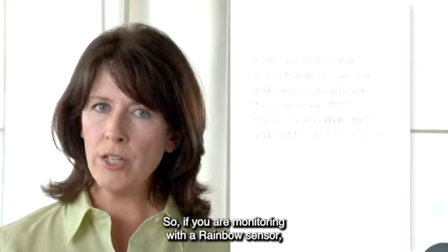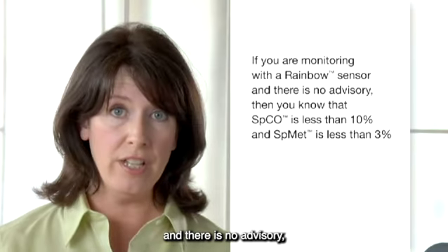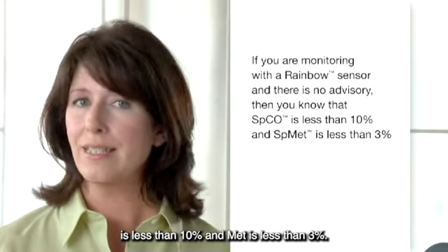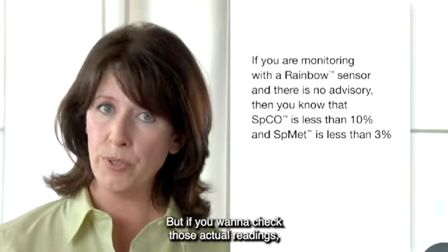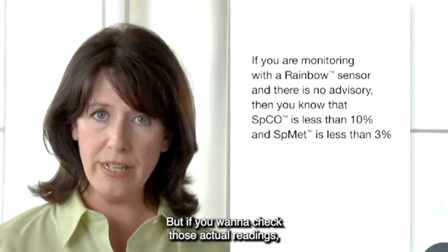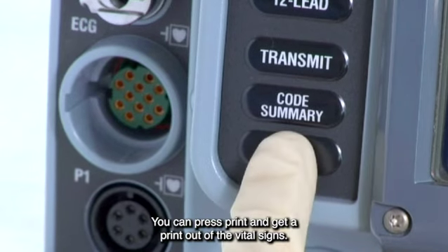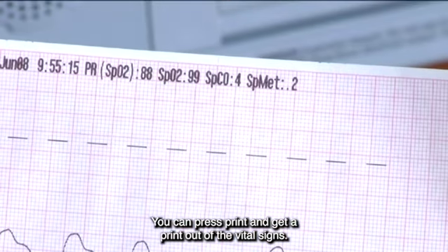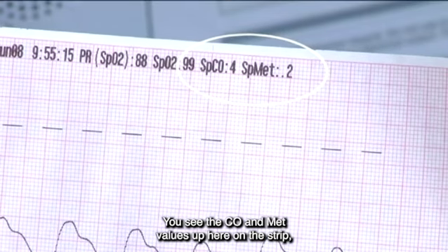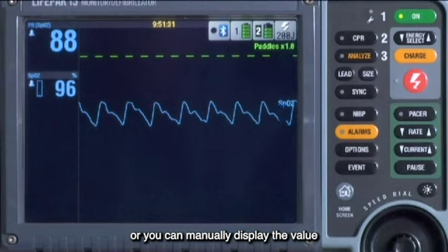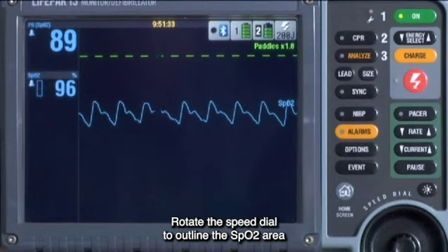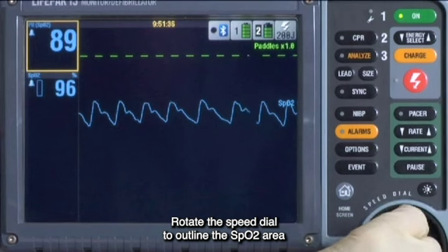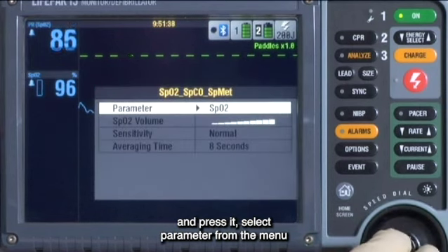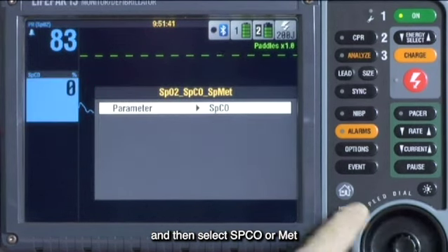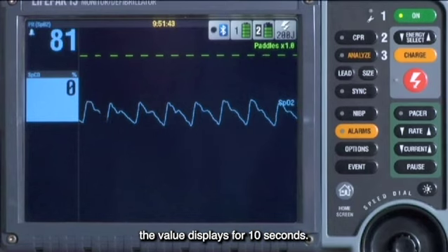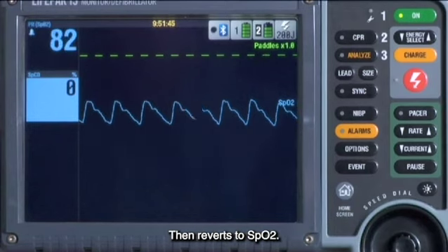So, if you are monitoring with a rainbow sensor and there is no advisory, then you know that the patient's CO is less than 10% and MET is less than 3%. But if you want to check those actual readings, there are two ways to do it. You can press Print and get a printout of the vital signs. You see the CO and MET values up here on the strip. Or you can manually display the value in the SpO2 area. Rotate the speed dial to outline the SpO2 area and press it. Select Parameter from the menu and then select SpCO or MET. The value displays for 10 seconds, then reverts to SpO2.